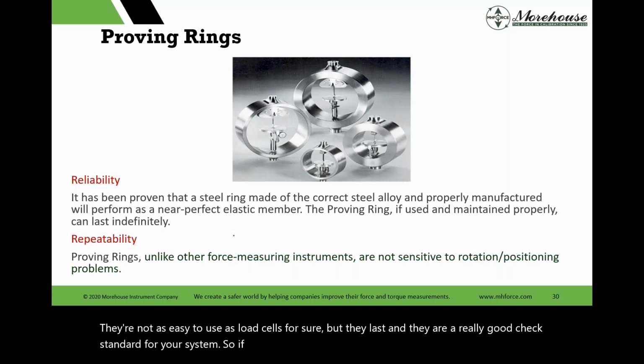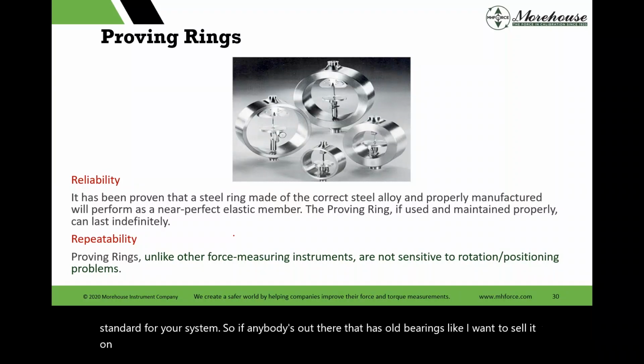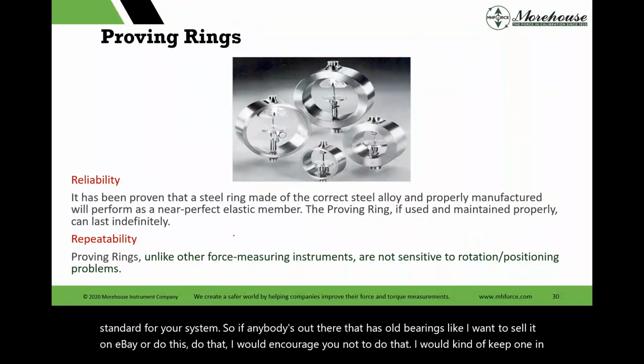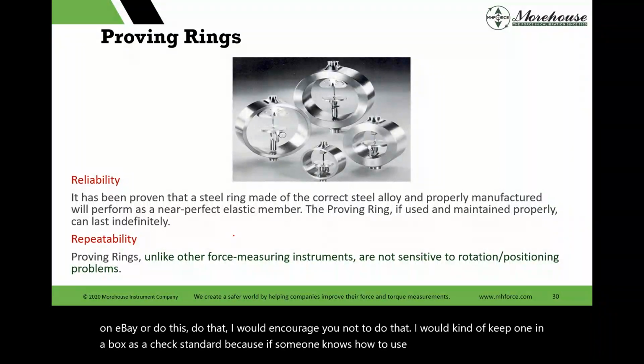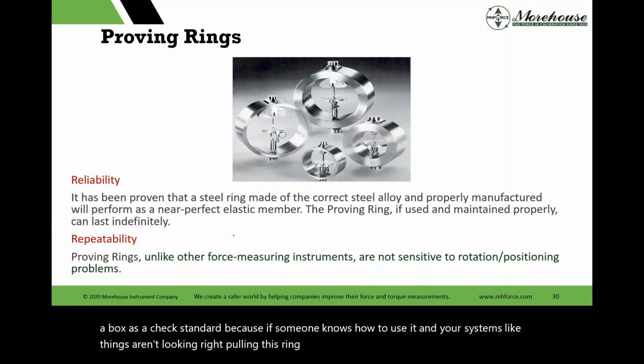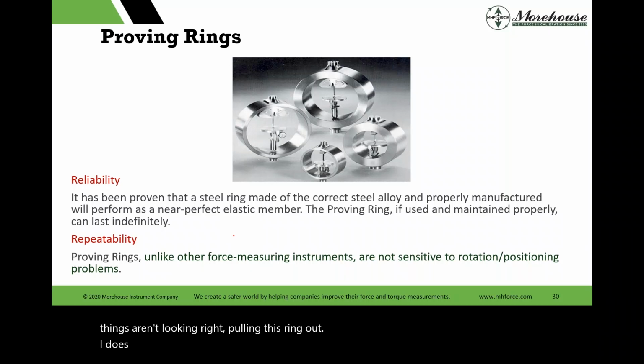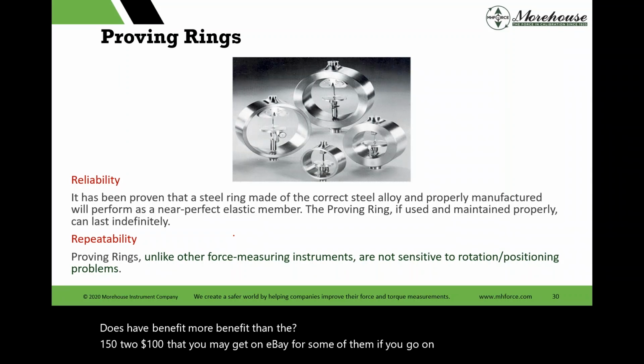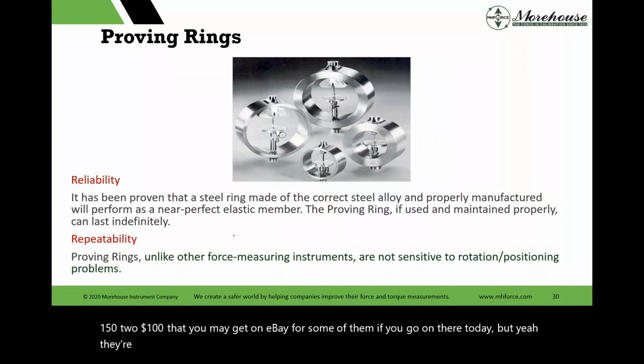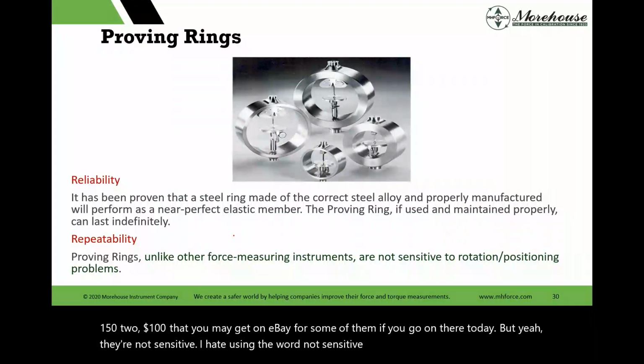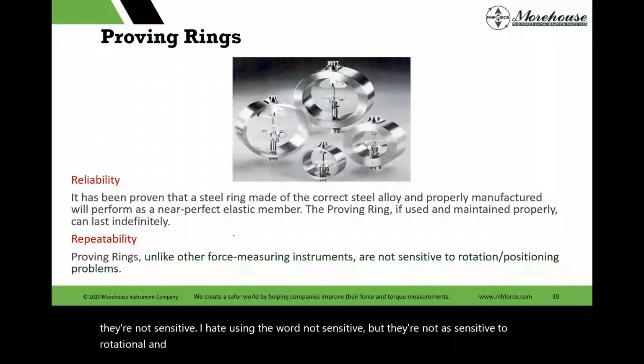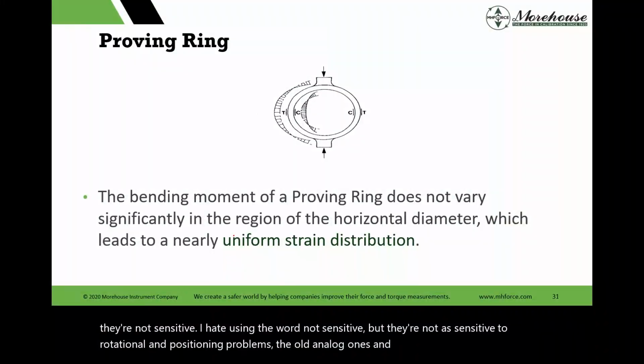So if anybody's out there that has old proving rings and wants to sell them on eBay, I would encourage you not to do that. I would keep one in a box as a check standard, because if someone knows how to use it and your system's not looking right, pulling this ring out has more benefit than the $150 or $200 that you may get on eBay for some of them today. But yeah, they're not sensitive. I hate using the word not sensitive, but they're not as sensitive to rotational and positioning problems, the old analog ones. And basically it's because of the bending moment of the proving ring.